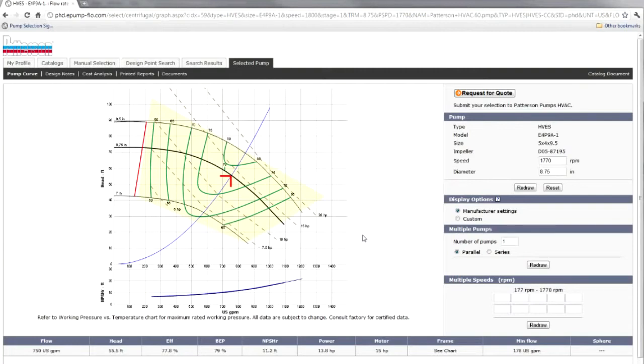So the horsepower is about the same, but this curve never goes over 15 horsepower, so the program has selected a 15 horsepower motor. So again, that helps us in our selection to decide what to do. This pump looks good. It's slightly less efficient than the other pump, but it is smaller. So now these are things that you have to evaluate. Do you want the higher efficiency and pay for that bigger pump?